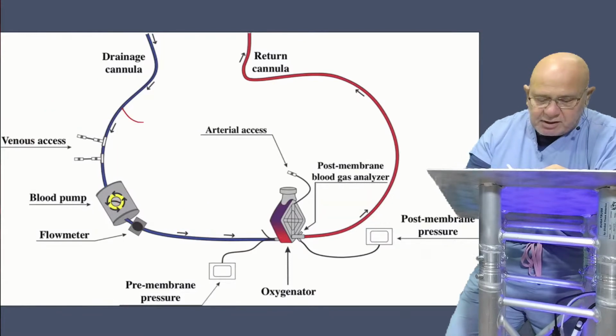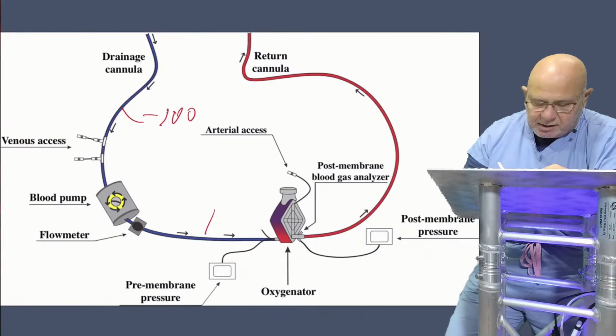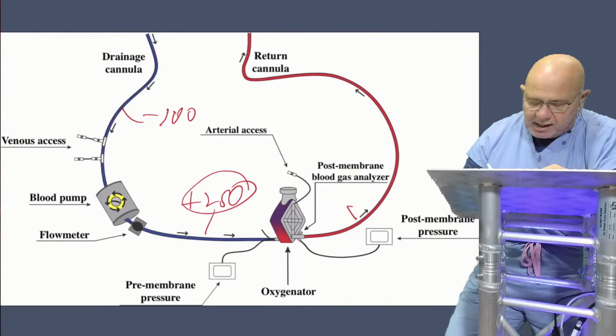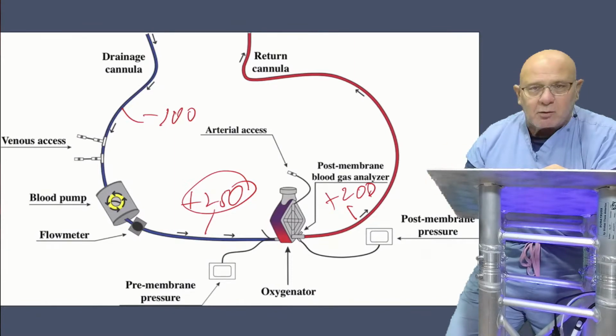If your pressure here is negative 100, your pressure here is positive 250, your pressure here is going to likely be lower than this pressure because you have the added resistance through the membrane. So we'll say it's going to be positive 200. It could be positive 180. It could be a little bit lower than that.